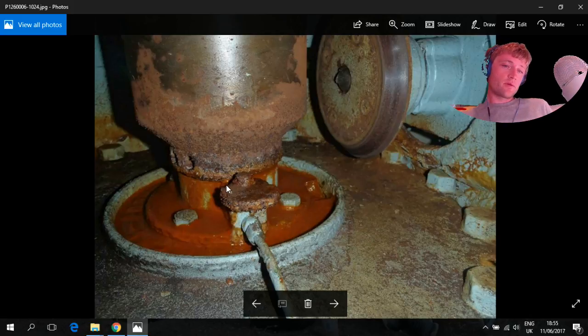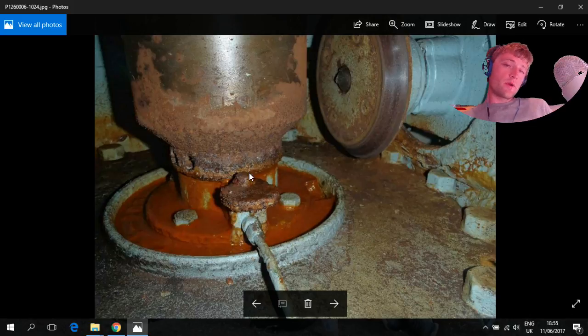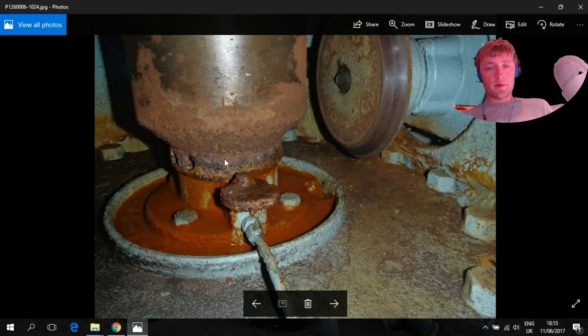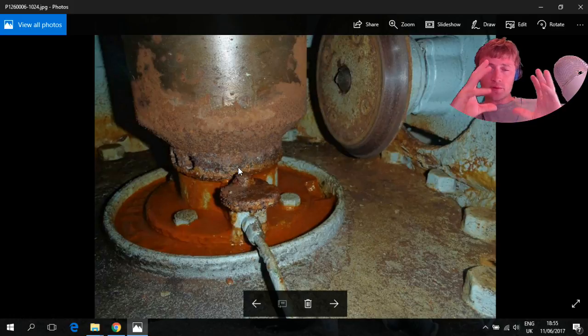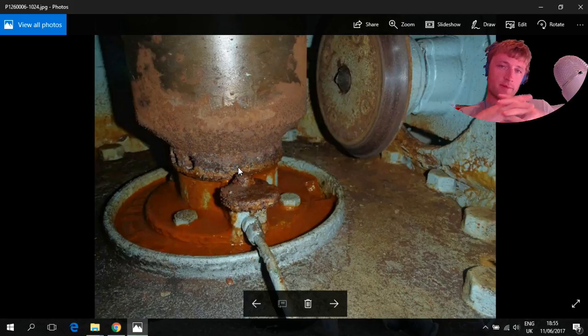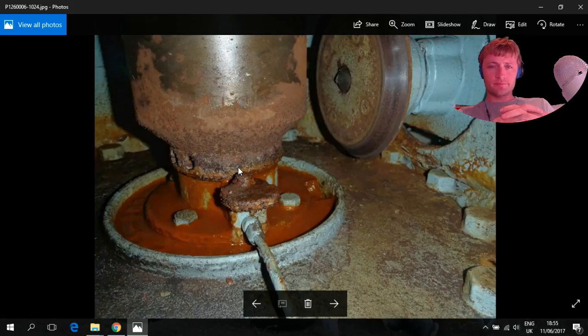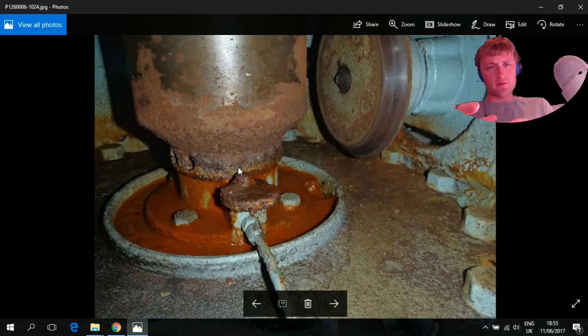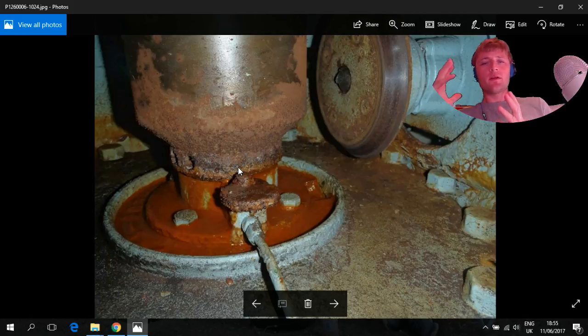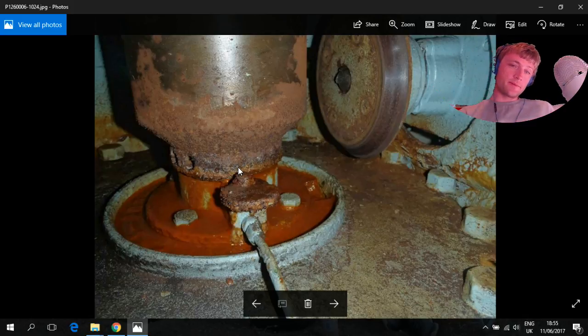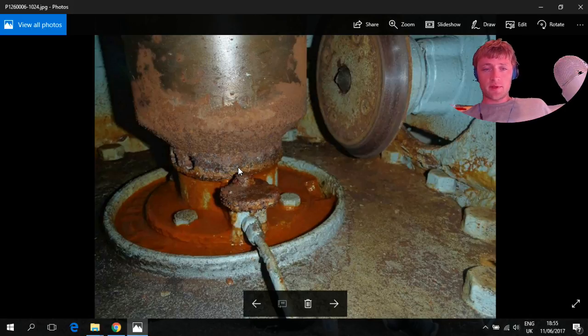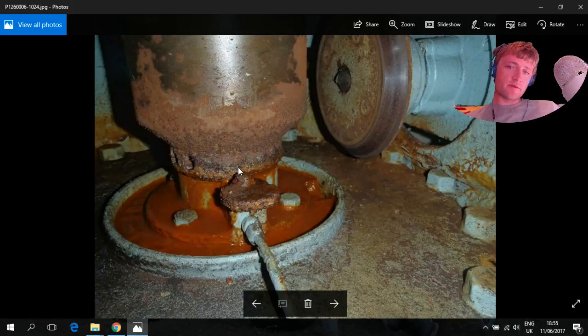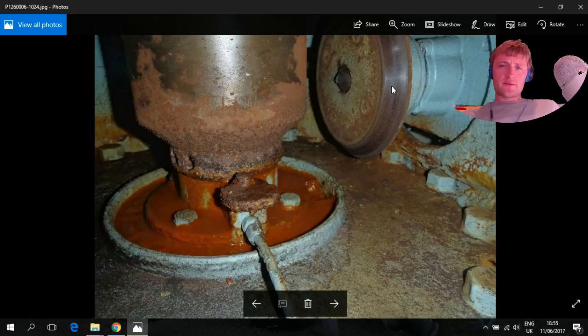This is a 13 number spanner—you just release this and turn to that side. When you remove your coupling here, your hydraulic coupling, because there is a hydraulic coupling which connects—I believe that with nuts it's much better. Because here in this system, if there's rust, you need first to remove the rust and it's more complicated. So if you have this system, it's better to fix immediately the problem of leakage, because after with the rust you have more and more problems.